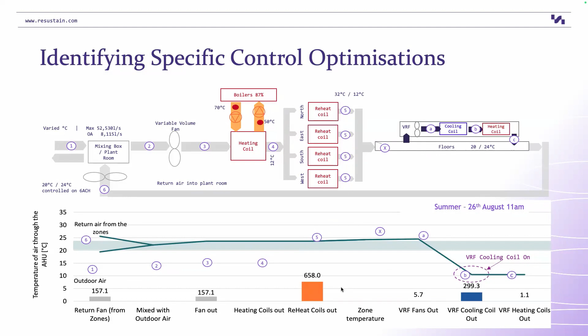What happens in the swing seasons? In the swing seasons, we've got the air coming in at around 14 degrees, return air at 25, mixes to about 16, goes across, and that heating coil doesn't do anything. The reheat coil is now on, takes it up to nearly 30 degrees. That goes into the spaces, and the VRFs go on to cool it. The VRFs cool it to 10 degrees when the outdoor temperature was about 13. So all of that energy is wasted. Could just be a nice straight line.